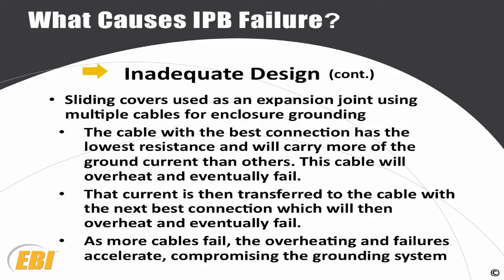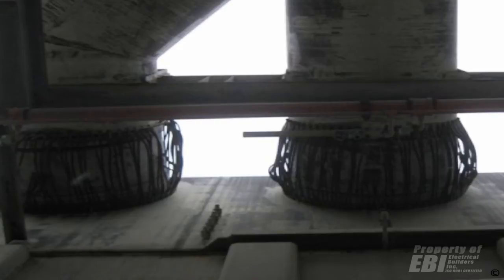One of the bus manufacturers uses sliding covers as an expansion joint. For this, you have to have a method to carry the enclosure ground currents from one side of it to the other, and they use cables. It's about 200 cables that jump from one side to the other. The problem is the cable with the best connection will carry the most current. It has the lowest resistance.